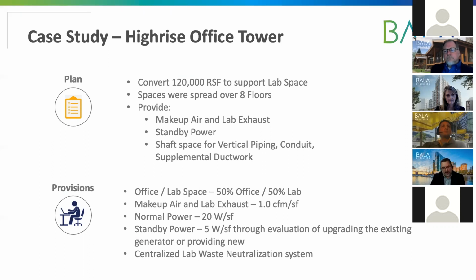So essentially, maximize a space that would accommodate 80,000 CFM of exhaust. And then from there, we work backwards into, okay, if we do 1 CFM per square foot for our typical average use, that would get us 80,000 square feet of lab space. And then if we mix it up between office and lab, we could get up to 120,000 square feet. So essentially, that's what we're looking at. We're dealing with a mixture of office and lab with a maximum of 120,000 square feet.